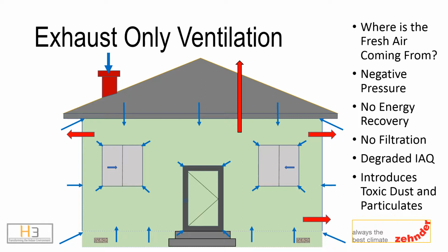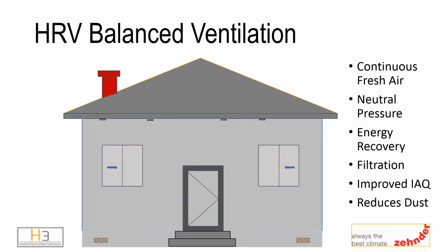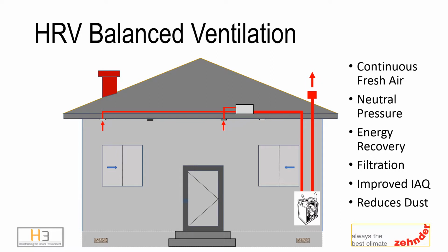We reached a time when we needed to reconsider Mr. Kirchmeier's invention of the HRV. Now let's look at the same house using a different ventilation strategy. We'll use an HRV to provide continuous fresh air ventilation. Exhaust ventilation is still implemented in areas such as kitchens, bathrooms, and laundry areas, but the system is balanced with fresh air being supplied to bedrooms, living room, and family room. Air is filtered to a high level, and heat or cooling are recovered from the outgoing stream and imparted to the incoming stream.